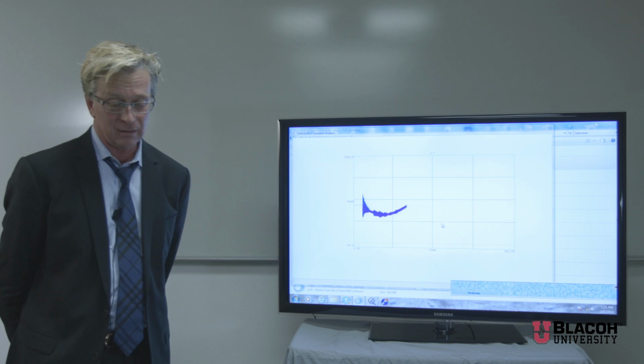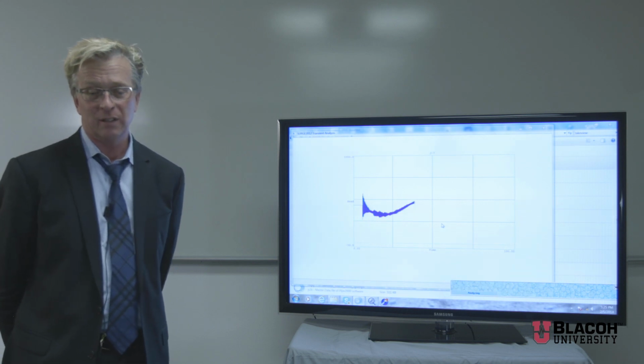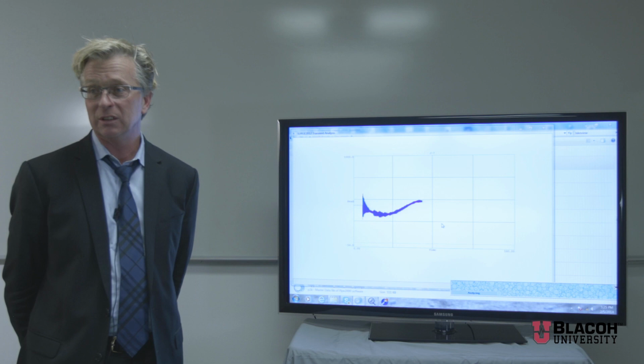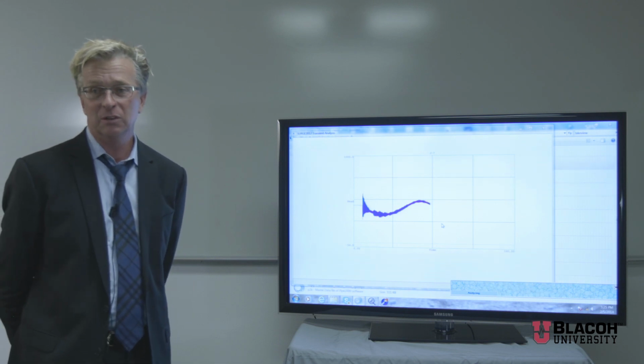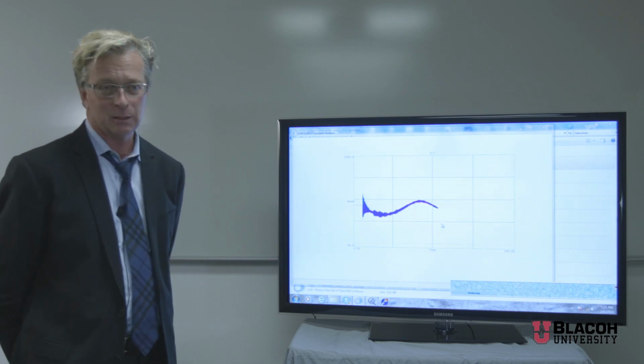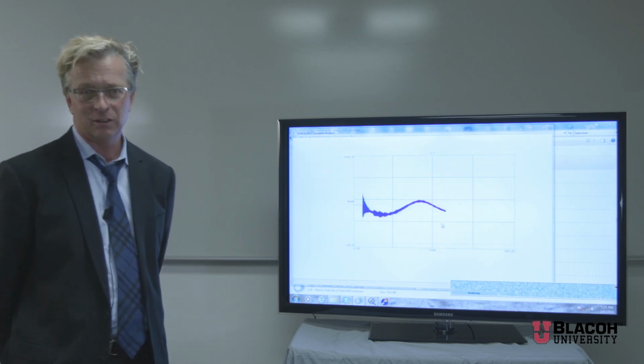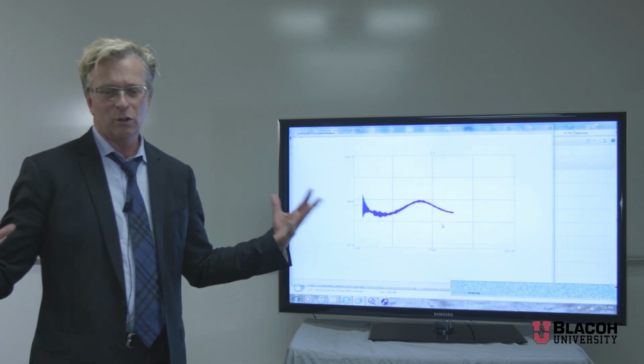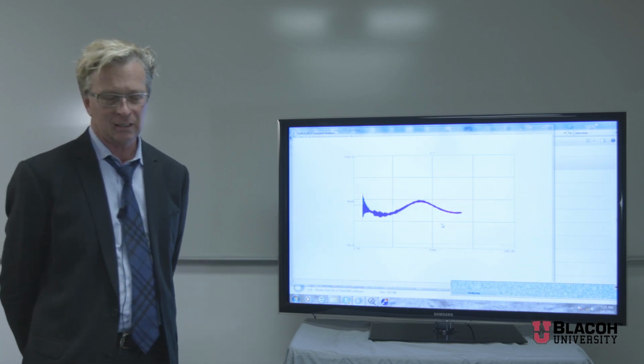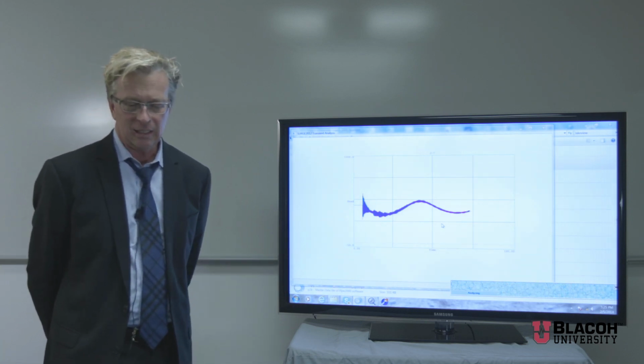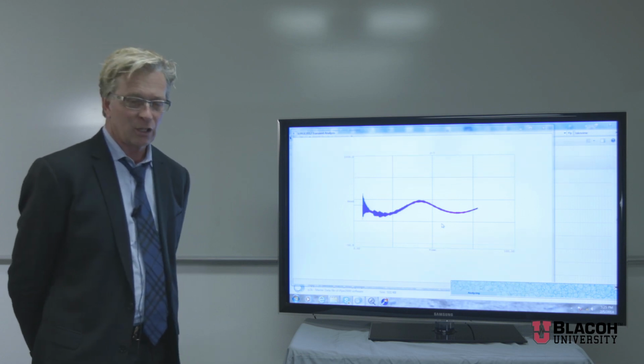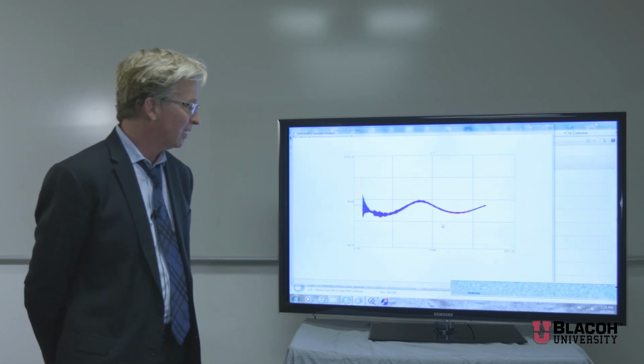So the initial disturbance, again, is the check valve closing and the shock wave created when those check valves close. Part of the issue in the model and in reality, again, this is a retrofit, is that the dampener and the surge device need to be as close to the pumps and the check valves as possible. Because between the check valve and the surge vessel, there's no protection in that piping, so that is subjected to that shock wave, as you can see in the initial part of the model. So again, as close to the check valve as possible is to the advantage.